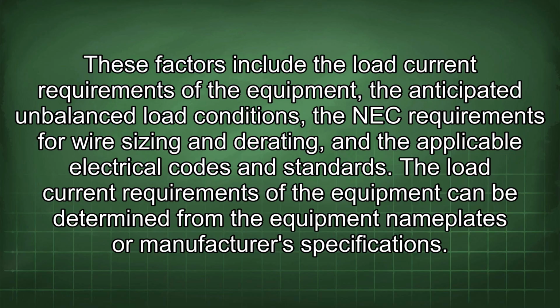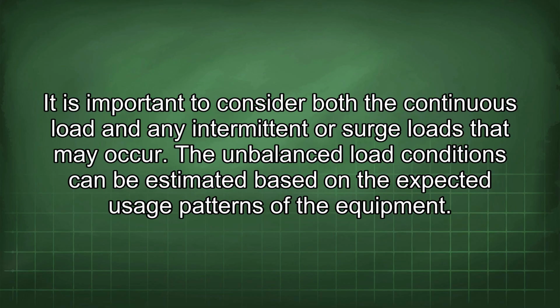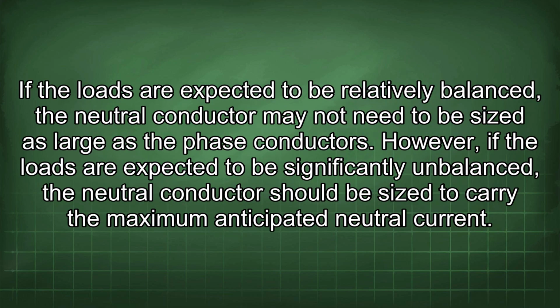The load current requirements of the equipment can be determined from the equipment nameplates or manufacturer specifications. It is important to consider both the continuous load and any intermittent or surge loads that may occur. The unbalanced load conditions can be estimated based on the expected usage patterns of the equipment. If the loads are expected to be relatively balanced, the neutral conductor may not need to be sized as large as the phase conductors. However, if the loads are expected to be significantly unbalanced, the neutral conductor should be sized to carry the maximum anticipated neutral current.